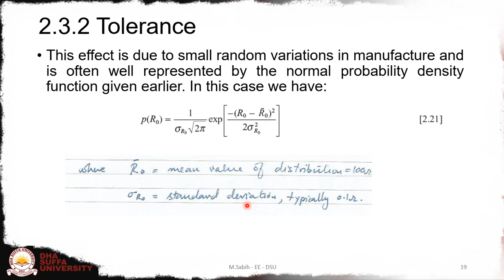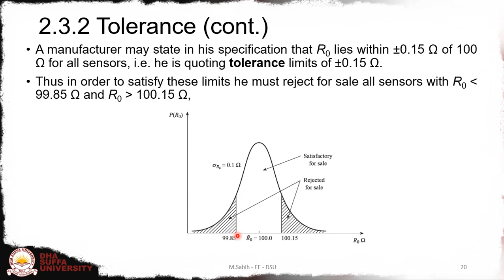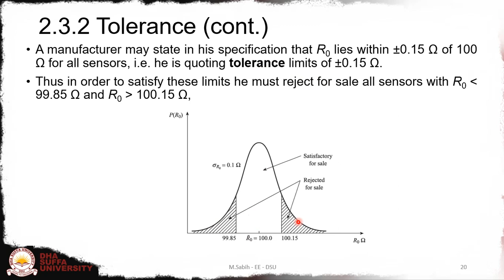A manufacturer may state in the specification that R naught lies within plus or minus 0.15 ohm of 100. So at any time you should expect the variation to be 100 plus 0.15 or 100 minus 0.15. In order to satisfy these limits, you must reject the sensors outside them. Once you have specified this, if the production unit produces something beyond the limit, that should be rejected. This is like quality control. So you will reject all the values which are less than 99.85, and also reject all the values above 100.15 ohms. This is satisfactory, provided that the tolerance is allowed and the users are okay with this tolerance, and the rest will be rejected.